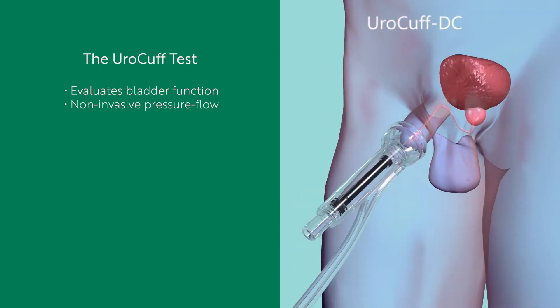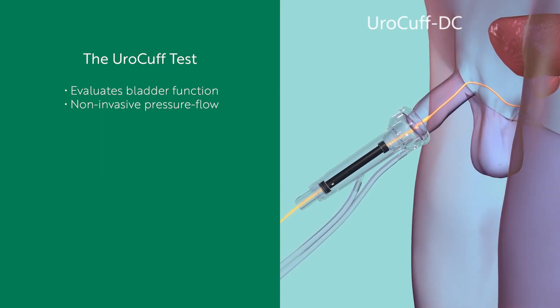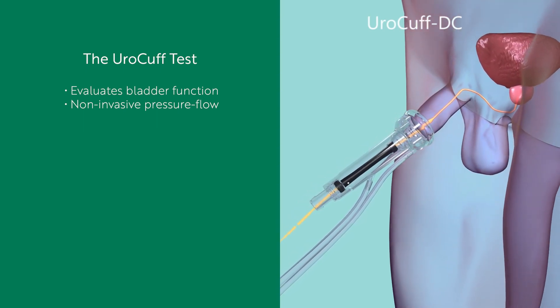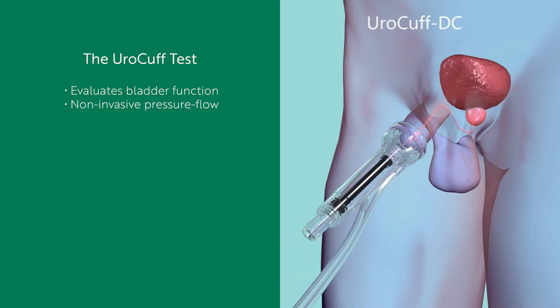The clinician will then start the test by pressing a button on the instrument. You will hear a pump in the instrument running as it makes the seal. Then the pump will stop, indicating the seal has been made. At that point, the clinician will instruct you to void. As you void, the device will apply a gentle pressure to the urine stream as it exits the body. Your bladder performance is determined by analyzing the changes in urine flow while the UroCuff applies the gentle pressure to the stream. The test is over when your bladder is empty.